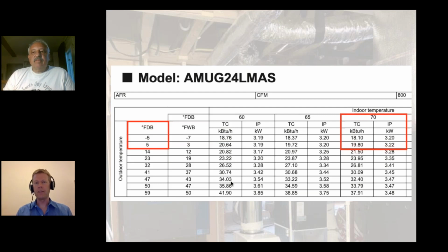Each manufacturer has their own lingo for what they call this, but this is kind of what it looks like. It's a table or a graph that shows outdoor temperatures and indoor temperatures and heating capacity or heating output and power input, so you can calculate COP. This is for a particular manufacturer's nominal 2-ton or 24,000 BTU per hour model that can put out 18,000 BTUs per hour at -5 degrees.